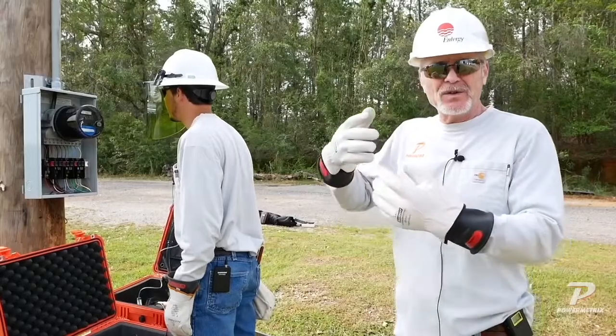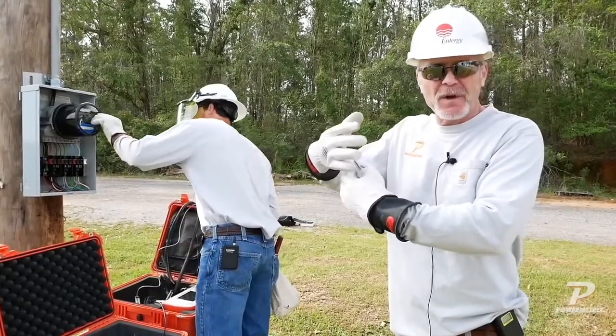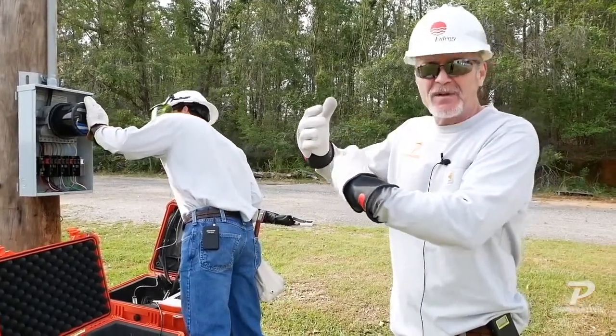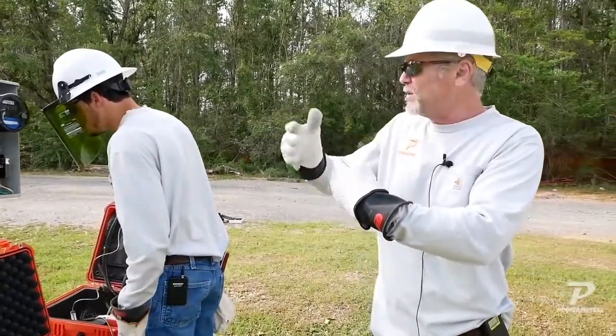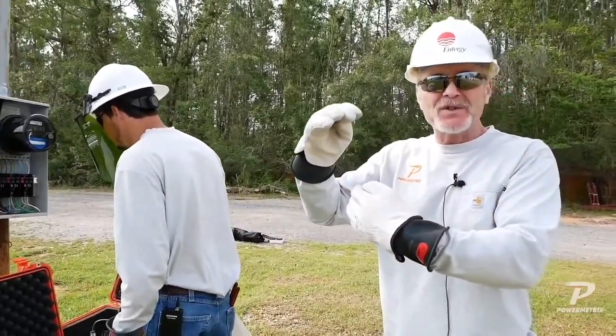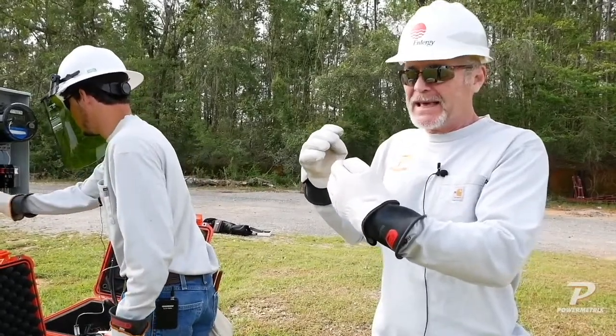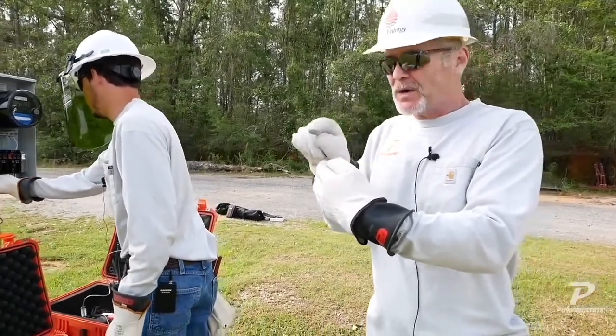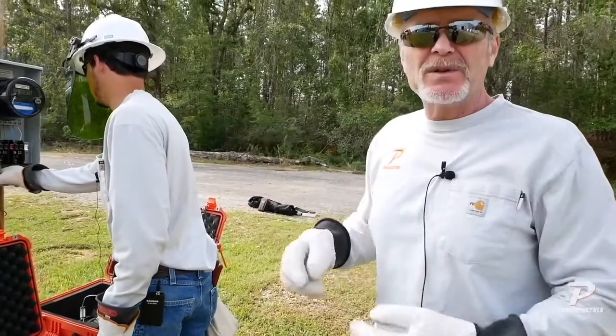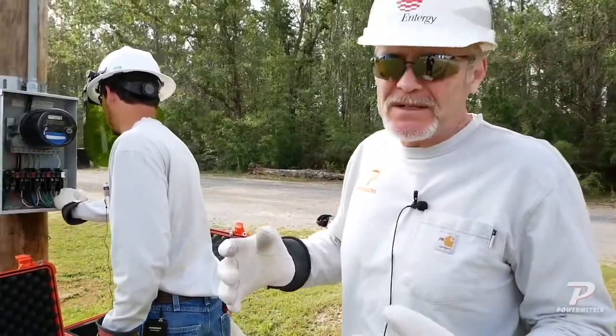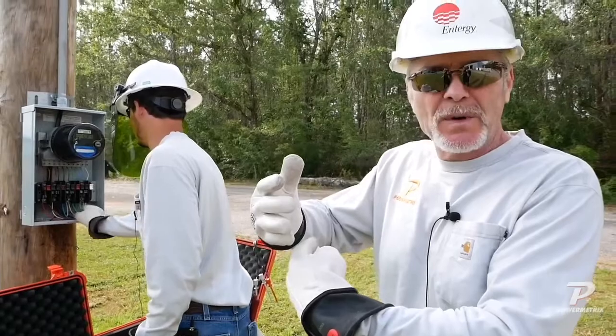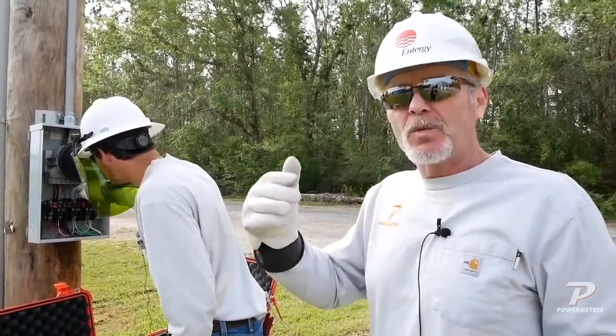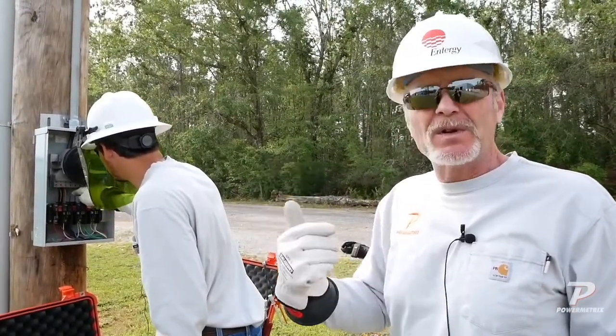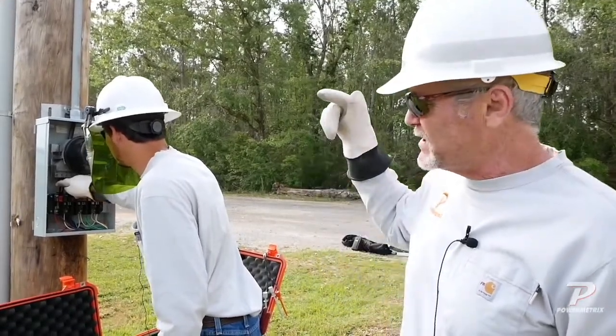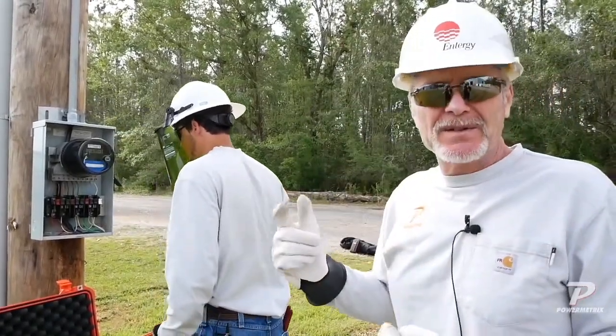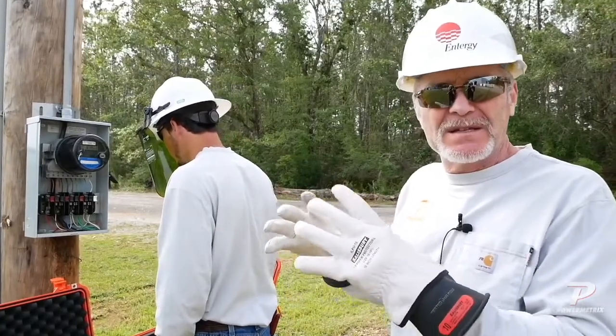And so you've always seen those comparisons in the webinars we've done before where it says, okay, I actually counted the pulses, my actual 1, 2, 3 with that pickup, but then when we measured it, it came out, well, we counted 3 pulses, but actually off of the measurements that we made, it should have been 2.995, for instance. It'll make a comparison of those two numbers, and that becomes your percent registration of accuracy for that meter under a customer load, where it's using all of the CTs, all the wiring, and everything else here. It's not a phantom load test. This is a customer load test.